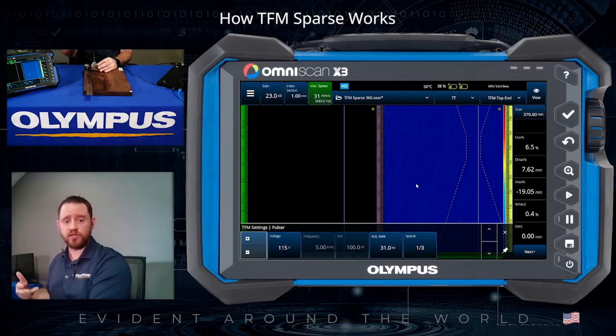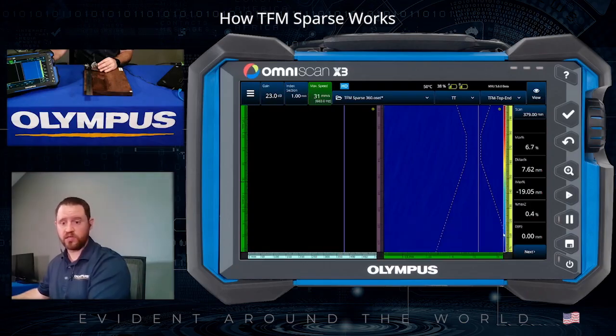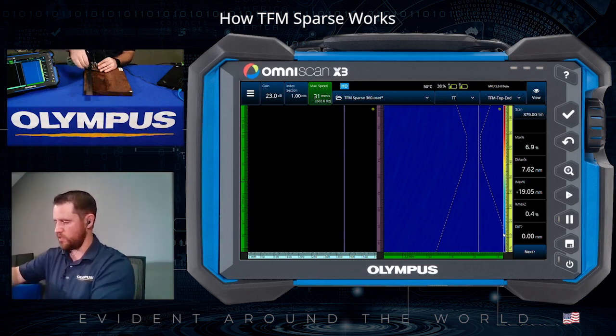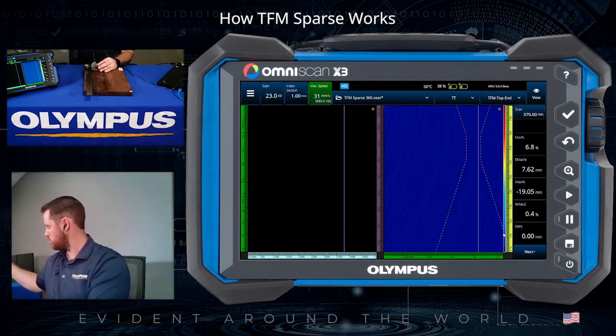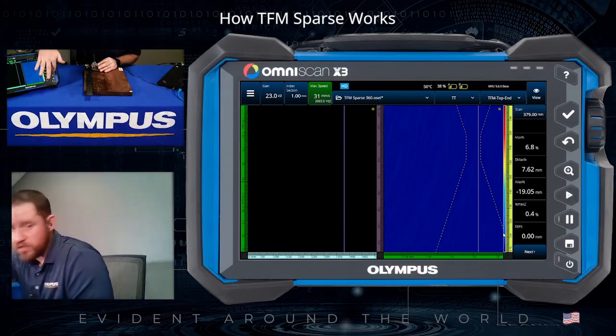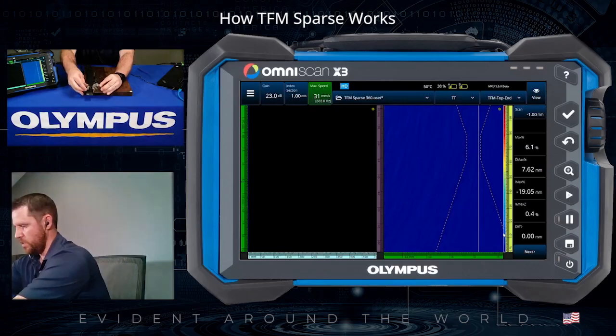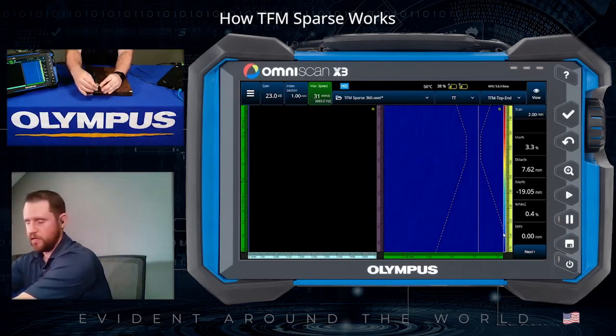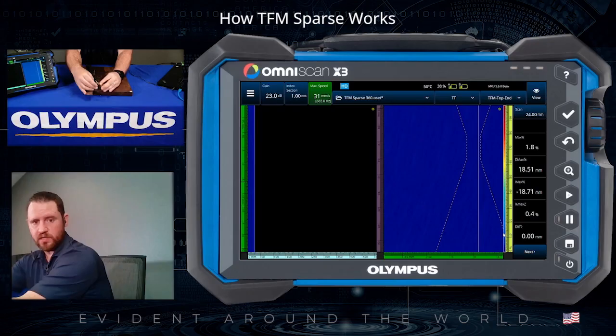And ideally what this is going to do is give us an increase in the acquisition rate for the system. You can see there as soon as it finishes adjusting that to the 1x3 sparse, we get a significant increase in our acquisition rate. So now rather than collecting at 11 millimeters per second, we are now collecting at 31 millimeters per second, which is a significant jump. So we'll add a little bit more couplant here just to make sure we're coupled well. I'll go ahead and reset my acquisition here on the unit. Realign my transducer and get a visual comparison on what kind of increase we see in the scan rate.